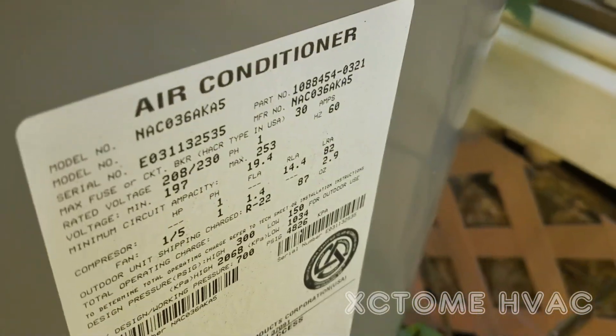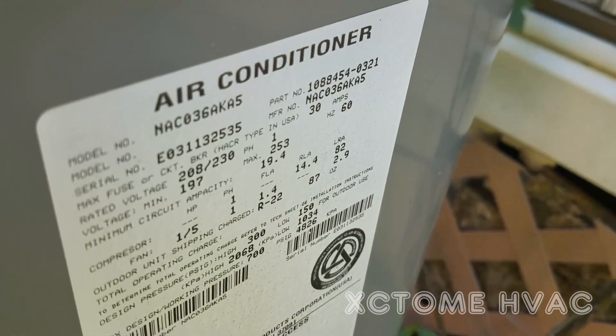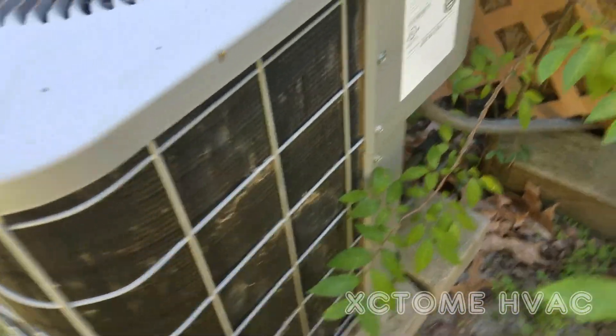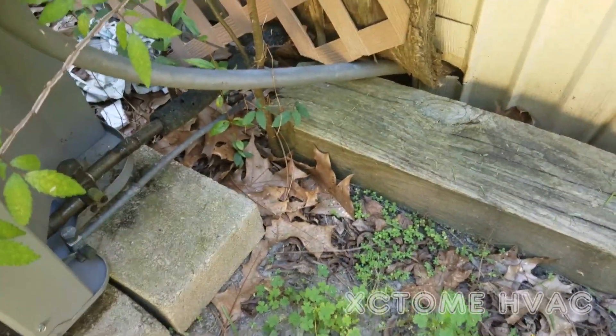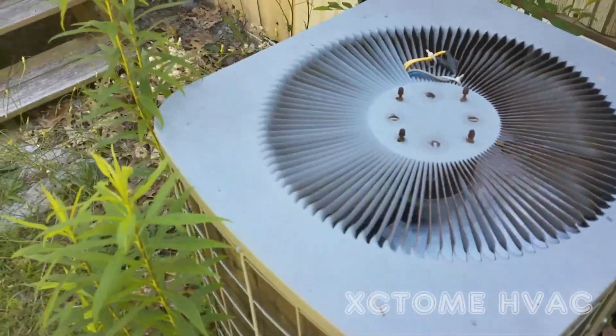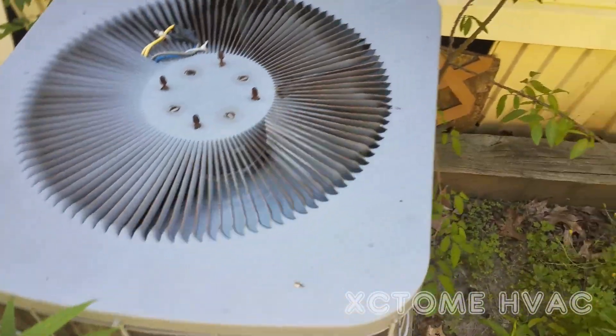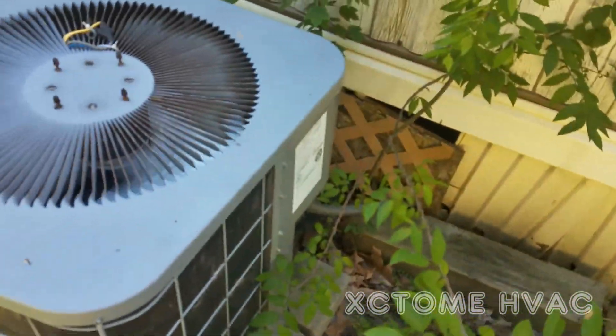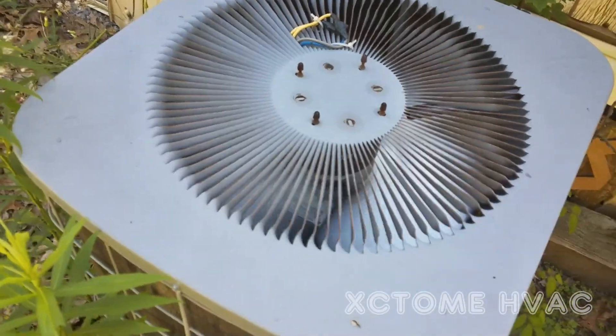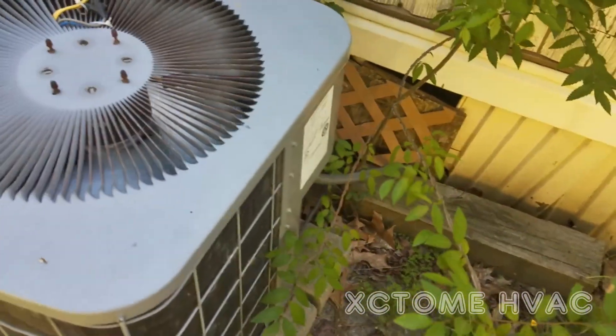It's a three-ton unit from 2003 — it looks lighter. That suction line is sweaty but not very cold. It's hooked up to a really old Coleman electric furnace that I had rewired around the same time I had the condenser fan motor put on, and that guy wired it incorrectly.